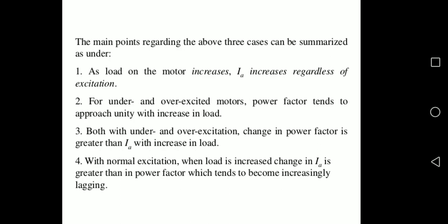For under and over excited motors, power factor tends to approach unity with increasing load. So whenever load increases, the armature current comes into phase with the reference voltage, in both under and over excited conditions.